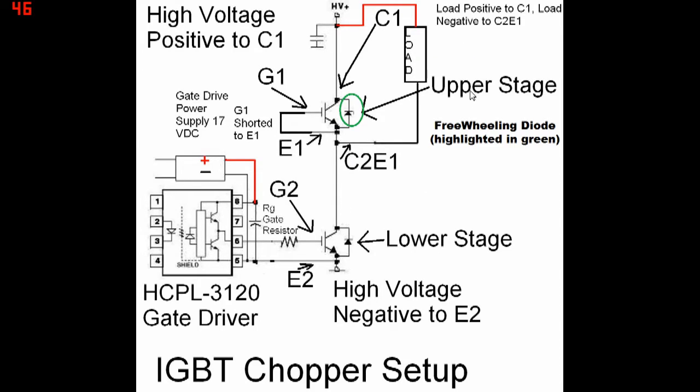When the IGBT switch is off, if we didn't have the freewheeling diode, the load's inductance would attempt to discharge through the IGBT, creating a very high voltage spike. So, when the load is switched off, when the IGBT switches off, the diode catches the load, or clamps the load's inductance, so that the IGBT won't experience a very high voltage spike.